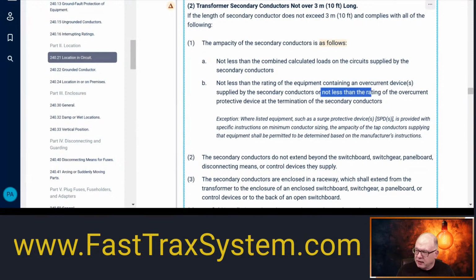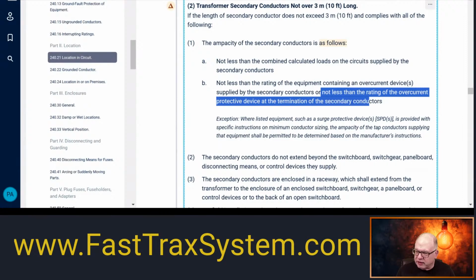Now it says, or not less than the rating of the overcurrent protective device at the termination of those secondary conductors. So this has to do with when it comes out of the transformer and hits a panel. If it's a panel enclosure, a remote distribution panel style, feeding that panel with a breaker and terminating in a breaker, then those conductors cannot be less than the rating of that device. So if those conductors are terminating in a 200 amp overcurrent device in a panel right next to the transformer, then they would have to be rated for 200 amps. Makes sense? If it was a 300 amp device, they've got to be rated for 300 amps. Makes sense? So, not less than the rating.